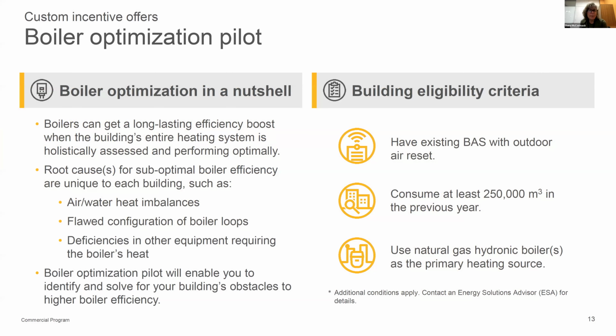This is new this year. It is our boiler optimization pilot. I'm just going to read from the slide, forgive me, because it really says everything I want to say. Boilers can get a long-lasting efficiency boost when the building's entire heating system is holistically assessed and performing optimally. So our approved delivery agents will go in and assess your heating system. They perform a series of audits and assessments to see where there are improvements to be made to increase your overall efficiency, including balancing and the configuration of your boiler loop. They'll look at your control system and see what can be optimized there. And this will enable you to reduce your gas consumption.